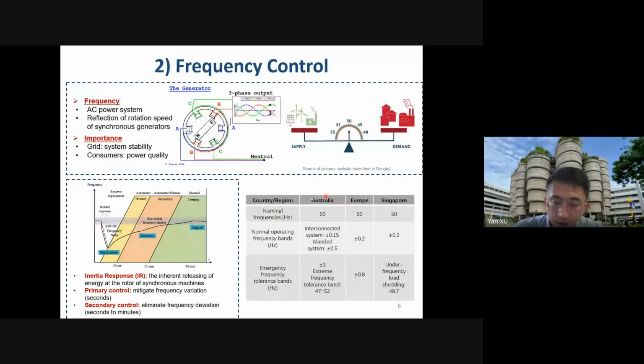Now, in this table, I'm showing the frequency standard as well as the tolerance. Very importantly, you should understand: theoretically speaking, the power supply and demand cannot be exactly balanced, because from second to second, minute to minute, every instantaneous moment, the load will be changing, right? Just for me, for example, if I turn off the light, I will decrease the total load of the system.